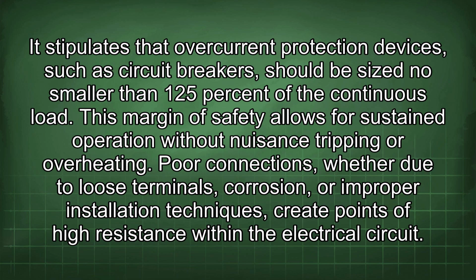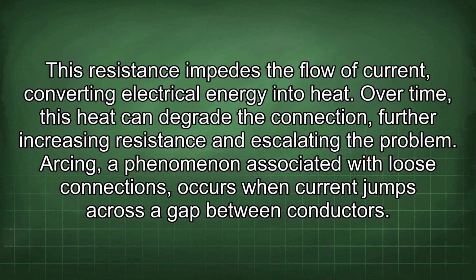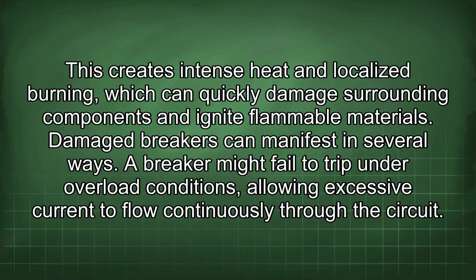Poor connections, whether due to loose terminals, corrosion, or improper installation techniques, create points of high resistance within the electrical circuit. This resistance impedes the flow of current, converting electrical energy into heat. Over time, this heat can degrade the connection, further increasing resistance and escalating the problem. Arcing, a phenomenon associated with loose connections, occurs when current jumps across the gap between conductors. This creates intense heat and localized burning, which can quickly damage surrounding components and ignite flammable materials.